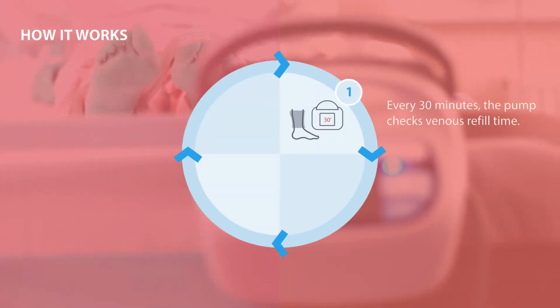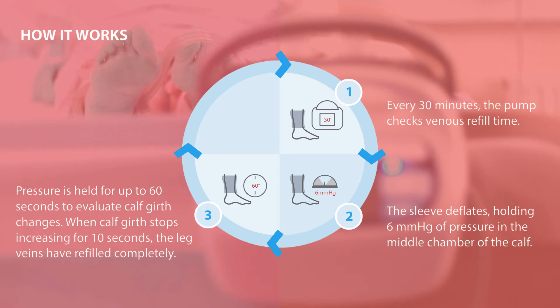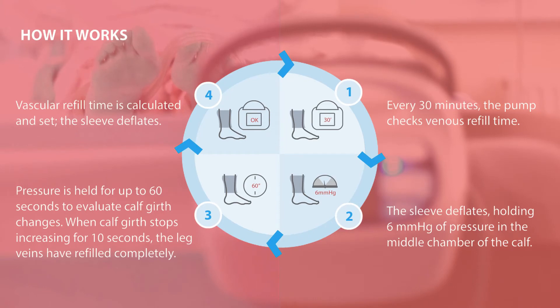Every 30 minutes, the pump checks venous refill time. The sleeve deflates, holding 6 mm of mercury pressure in the middle chamber of the calf. Pressure is held for up to 60 seconds to evaluate calf girth changes. When calf girth stops increasing for 10 seconds, the leg veins have refilled completely. Vascular refill time is calculated and set. The sleeve deflates.